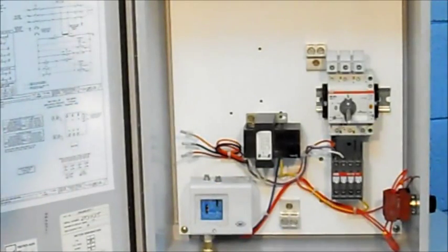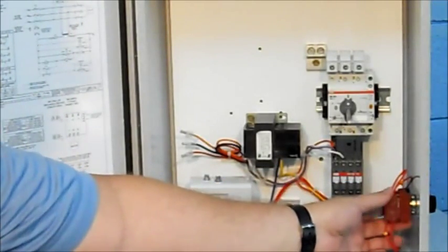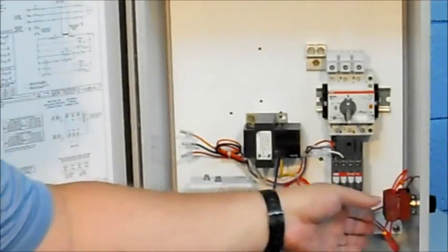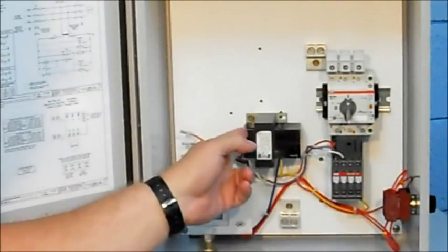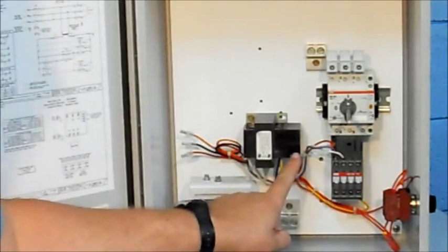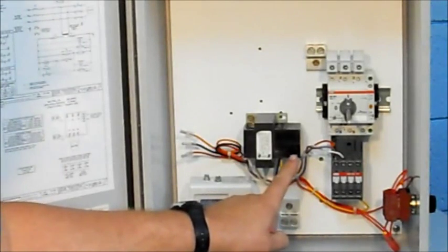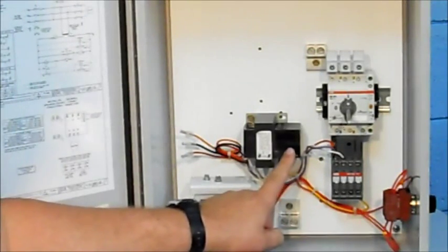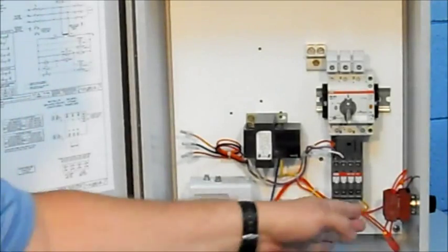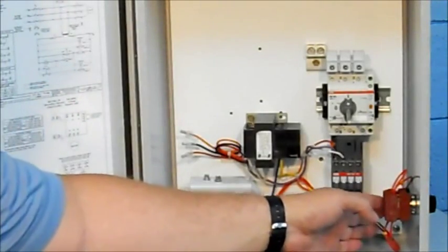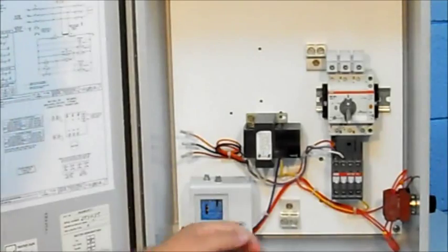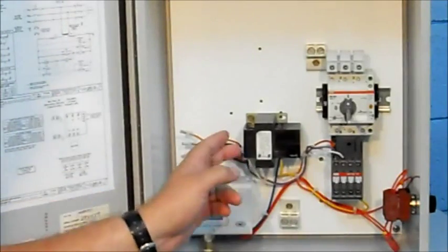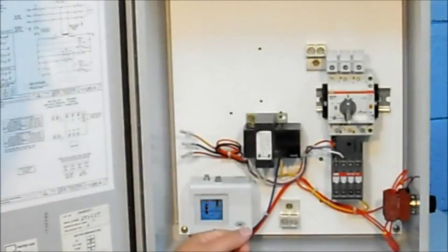If you do not have the voltage, and your selector switch was in the hand position, then you may either have a failed transformer, the transformer reset may have tripped for some reason and needs to be reset, or you may have a problem in the selector switch contact block itself. Tracing your voltage through those devices will allow you to troubleshoot that.